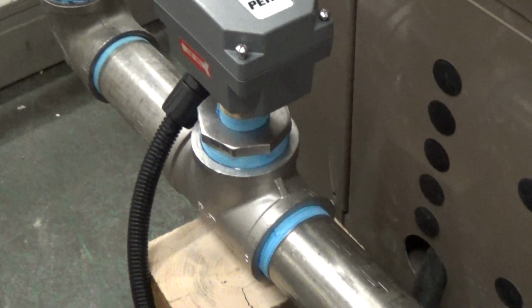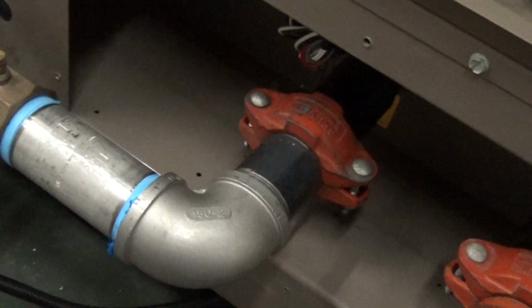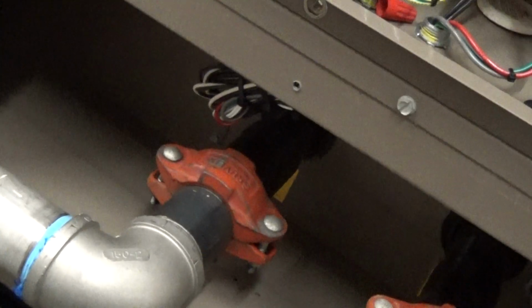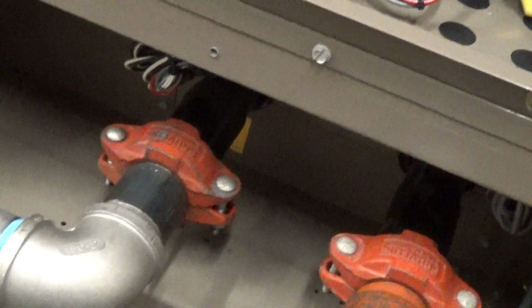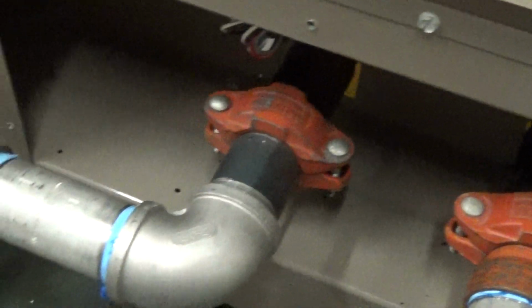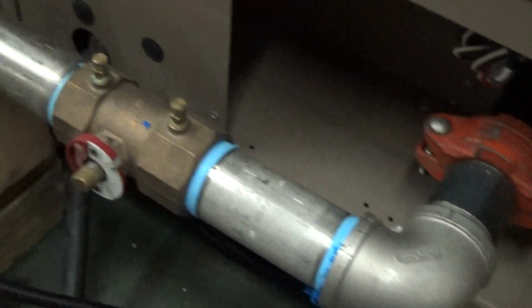You want to put that on your outlet piping, and typically you want to make sure it's at least 5 diameters away from the heat exchanger. But in this case, the heat exchanger is farther in behind the edge of the chiller here, so as long as you have it right here in the next foot or two, it's fine. That's a 2-wire connection, the flow switch, and you can see we kind of snake it right here. And this is all in the manual, but you want to connect it to your terminal block on the right here, and it's 13, which is the common, and 14. Okay, that's your flow switch, so you want to tie right into the terminal block on the chiller.